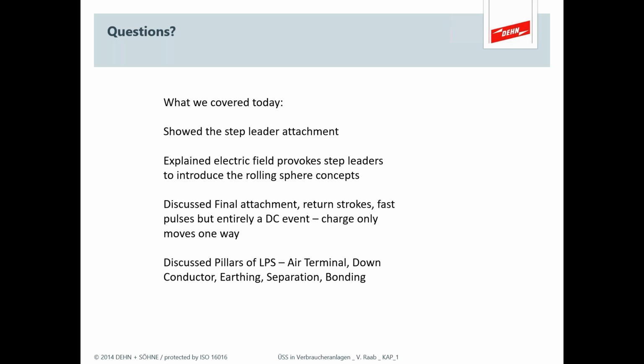Yes, Mohammed, what I can say is, the type B earth electrode that IEC describes in 62305 only consists of a grounding ring that is installed around the structure. You can include earth rods to increase the conductor that you need to have in contact with the soil, but as it is in IEC as a type B, it does not include earth rods. Earth rods are considered a type A grounding system, but if we do the calculation to determine the length of conductor we have to have in contact with the soil, you can increase that by adding earth rods as well.